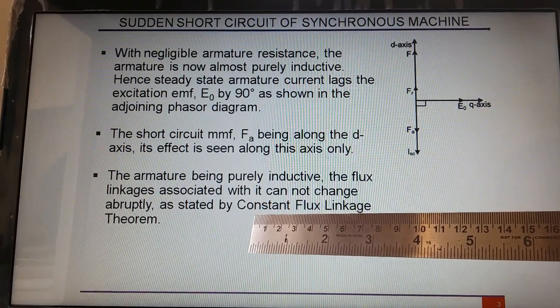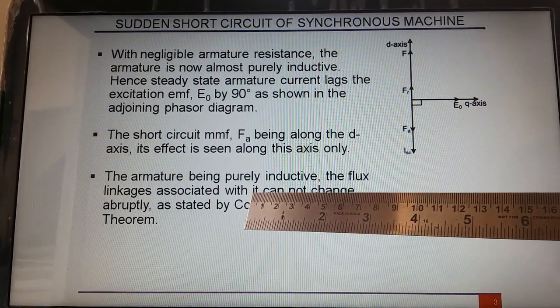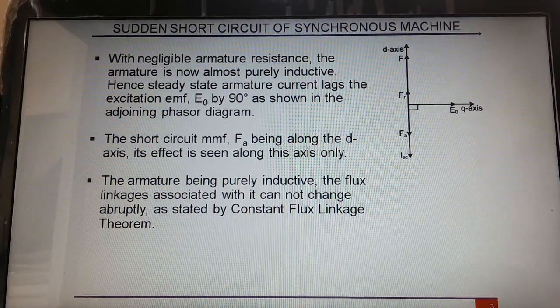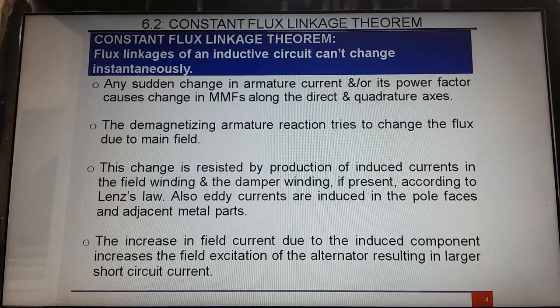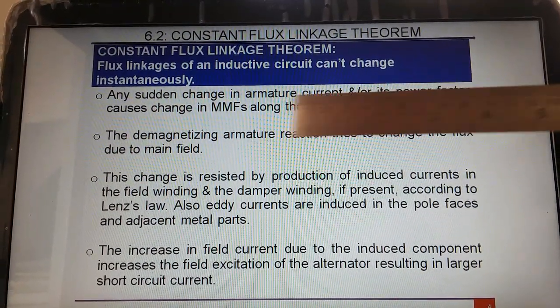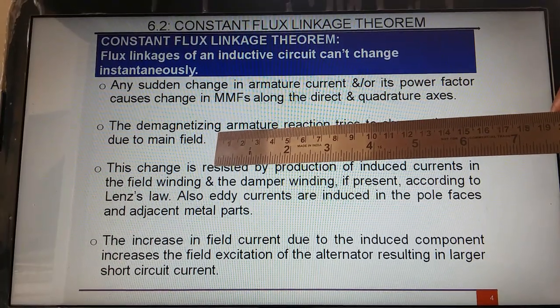The short circuit MMF Fa being along the d-axis, its effect is seen only along the d-axis. Since the armature is purely inductive, flux linkages associated with it cannot change abruptly. The moment short circuit happens, sudden current appears in the circuit, and because of it, additional flux will come in the air gap. This flux cannot change suddenly — that statement is termed the constant flux linkage theorem, which states that flux linkages of an inductive circuit cannot change instantaneously.